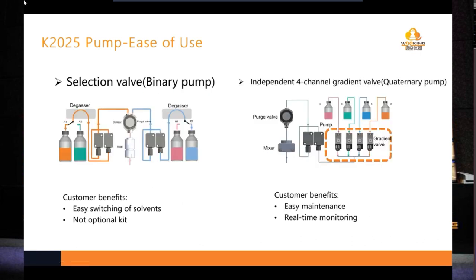And the selection valve is for the binary pump. By using this valve, we can easily choose which solvent to use and switch to another one when needed. It is not an optional kit. And for the quaternary pump, we have a patented 4-channel gradient valve. Each channel is independent and can be replaced easily without changing the whole valve. And each channel can be monitored.